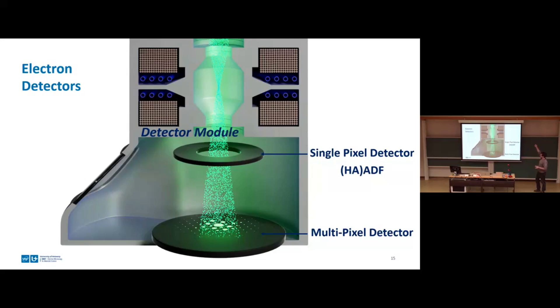And this is as far as the simplified model that we put together of the microscope, but how do you use it? The most common way to use this microscope is two ways. CTEM, conventional transmission electron microscopy, is analogous to the biology lab microscope, in which a parallel wave or a plane wave illuminates your sample, as you can see there. And then the electrons that scatter at the sample are collected by a lower objective lens, and they can be focused in the back focal plane of that lens, and give you a diffraction pattern. Or you can create a magnified image if you project them in a conjugate image plane afterwards.